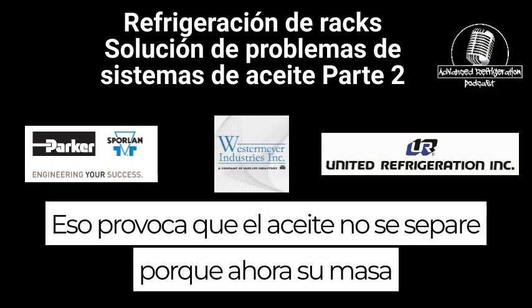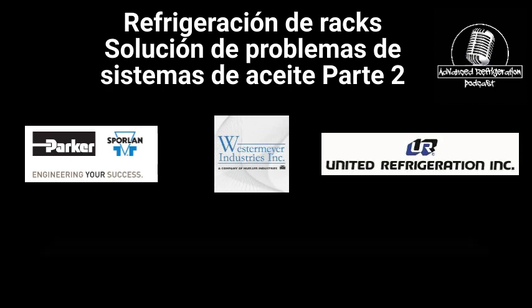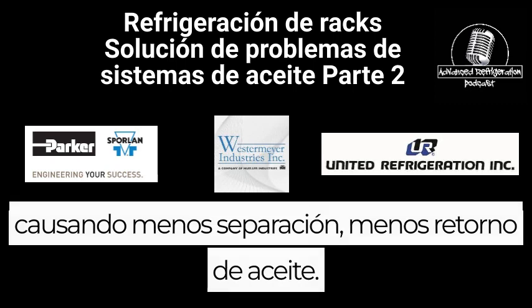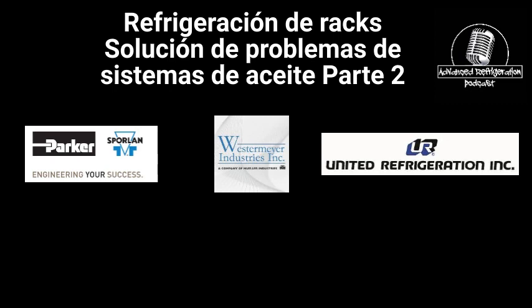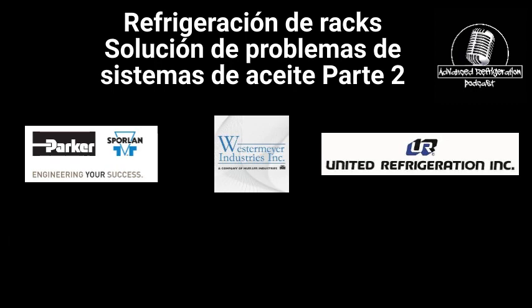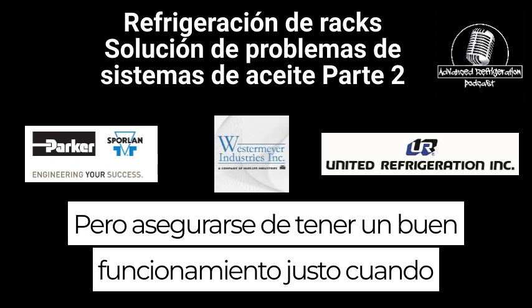That causes oil to not separate well, because now your mass flow is lower than it should be on a suction. So now you have less oil returning back to the compressors, and you end up causing less separation, less oil return. Another big thing is making sure your suction filters are clean and pulled. I prefer them pulled. Make sure you don't have any restrictions on those suction filters, because if you do, that's going to greatly reduce your oil return to compressors. So, make sure you have a smooth running rack when you have oil issues.